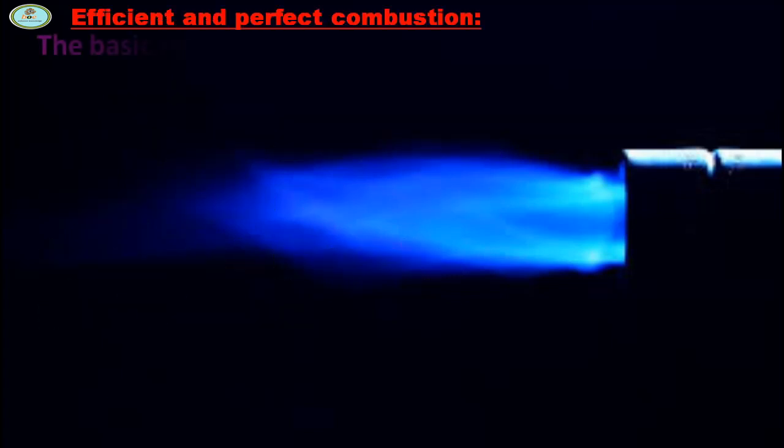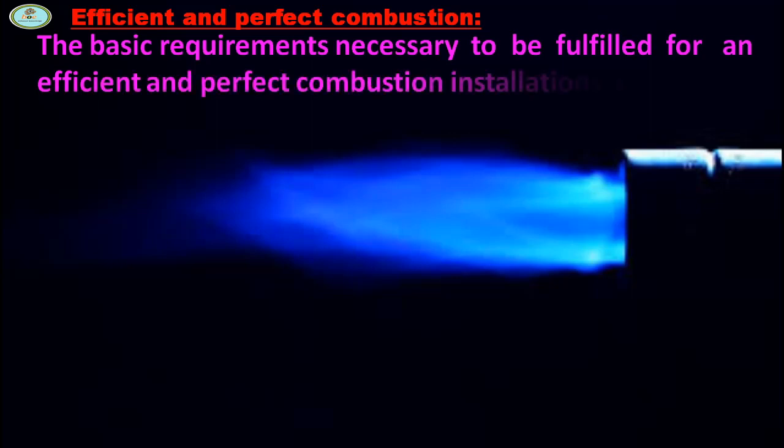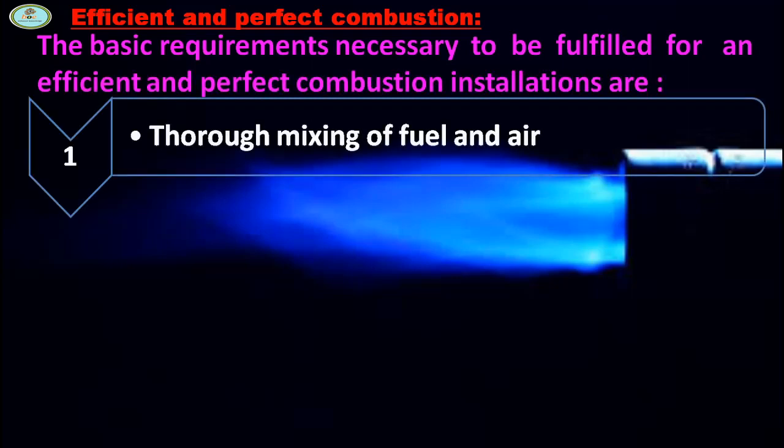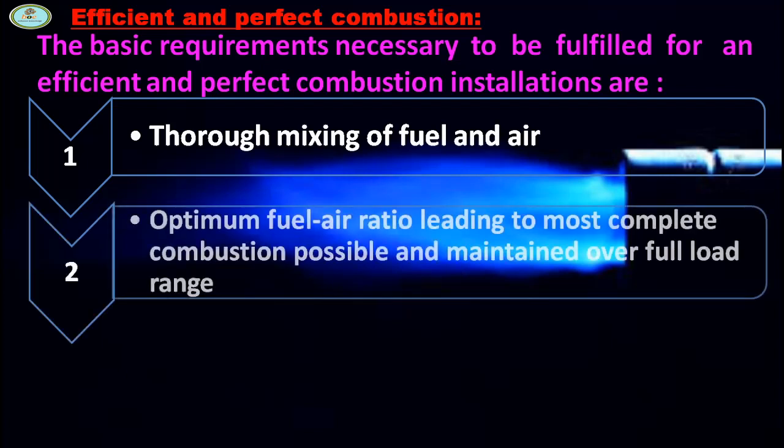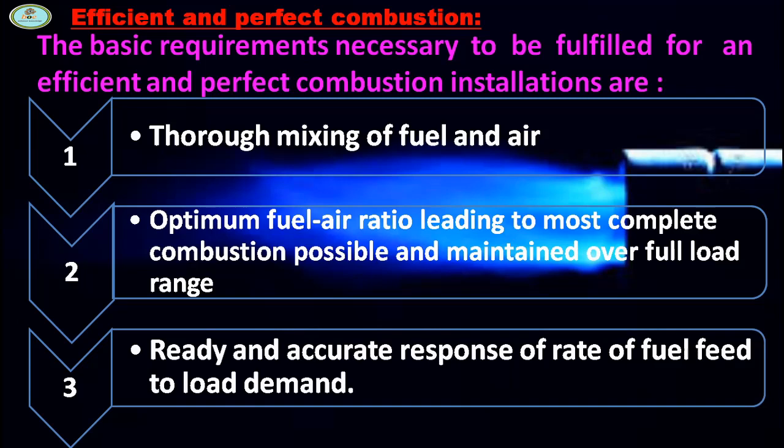The basic requirements necessary to be fulfilled for an efficient and perfect combustion are as follows: thorough mixing of fuel and air, optimum fuel-air ratio leading to most complete combustion possible and maintained over full load range, optimum fuel-air ratio leading to few emissions, ready and accurate response of rate of fuel feed to load demand.